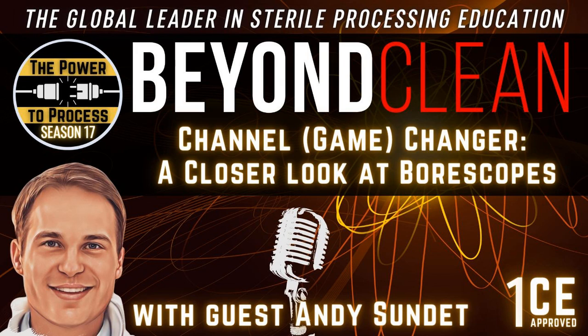That is a fantastic point. I hadn't really thought about that, but yes, obviously the smaller diameter scopes aren't nearly as long as the GI scopes. So knowing the types of scopes that you're going to be inspecting, the types of scopes that are in your department. And then I really like what you said about laying it out, because I can imagine if you're trying to coil it, getting the borescope to pass through a flexible scope that's coiled is going to be a lot more difficult than having that flexible scope laid right out straight so that the channel is pretty much linear. There'll be some variation, but I can imagine it's a lot easier to pass a borescope through a flexible scope that's laying out straight.